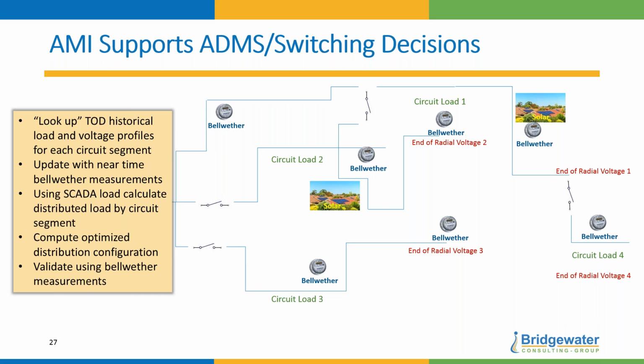Well, what happens if you have a bunch of bellwethers and start looking at them? You'll get a much more precise load flow model, which you can put into the model instead of just estimating values, especially at the ends of radials. The bellwether data, maybe a minute or two old, is fine when you're doing load switching, fault restoration, or a scheduled outage—you can optimize your switching based on that data and historical information.